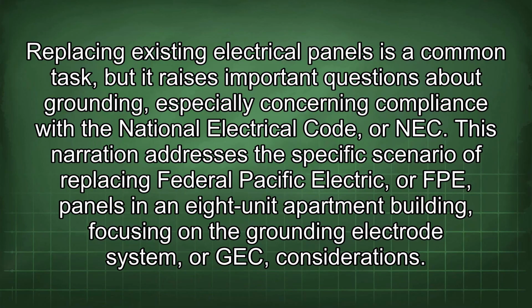Replacing existing electrical panels is a common task, but it raises important questions about grounding, especially concerning compliance with the National Electrical Code, or NEC. This narration addresses the specific scenario of replacing Federal Pacific Electric, or FPE, panels in an 8-unit apartment building, focusing on the grounding electrode conductor, or GEC, considerations.